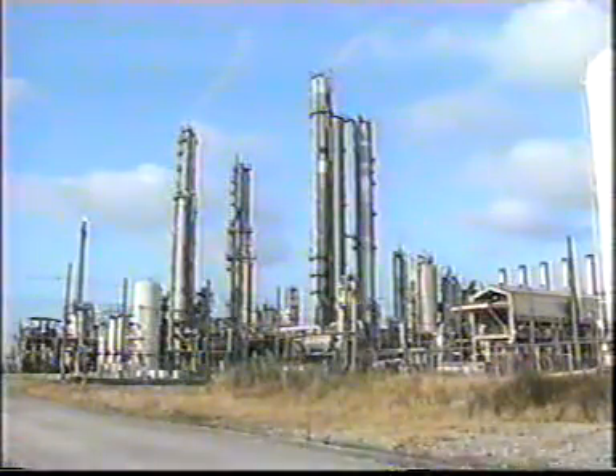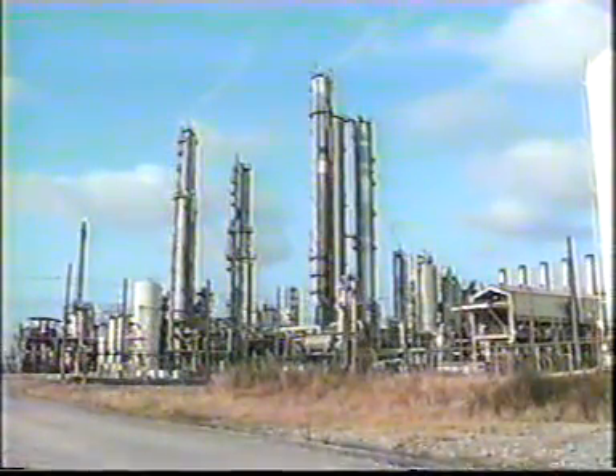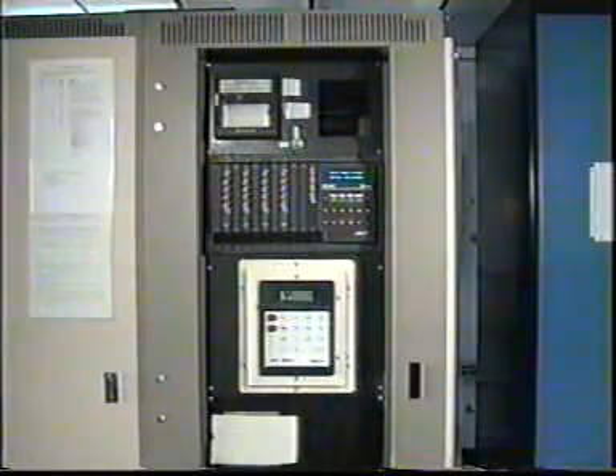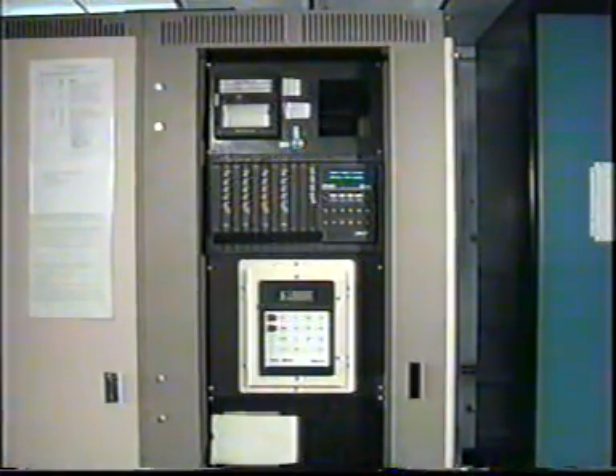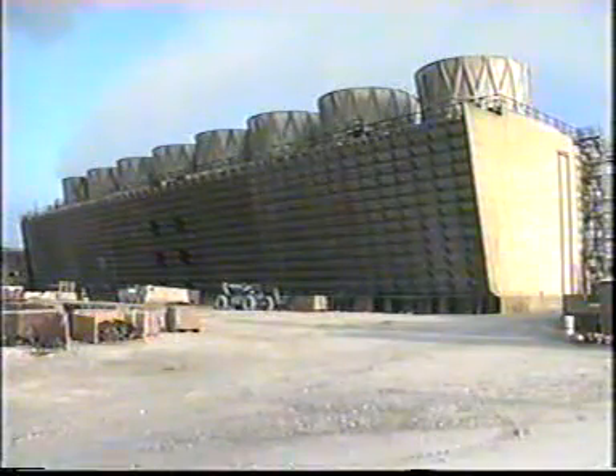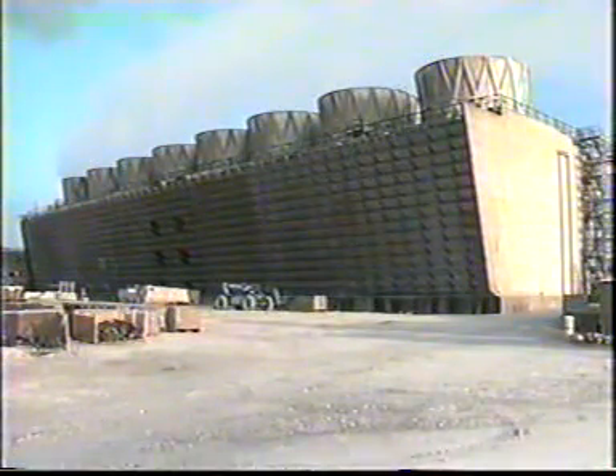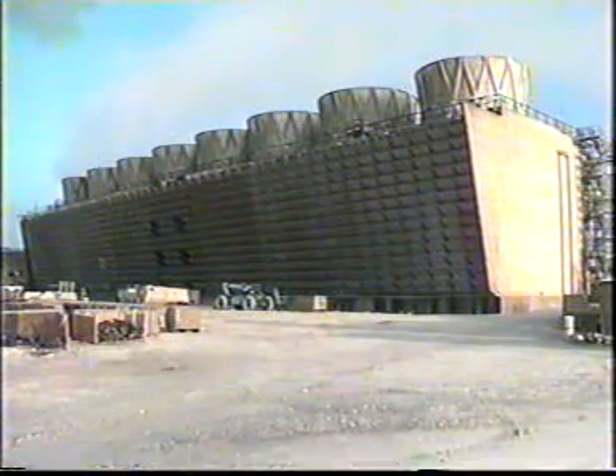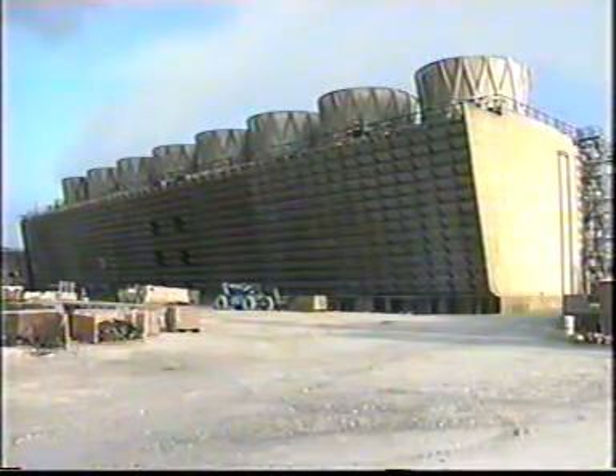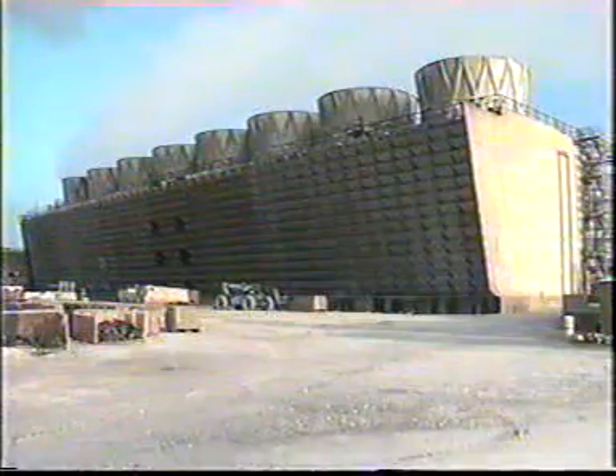Some systems will have more than one sensor to activate a shutdown. Logic circuits in the monitoring unit can vote whether or not to shut down the machine. The conditions necessary could be time, vibration amplitude, the number of sensors sensing a high vibration, or a combination.